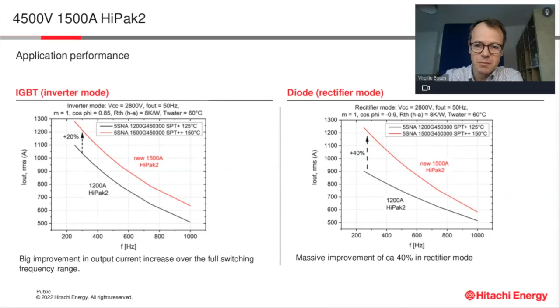Now, if we look at our press pack IGBT, which we call StakPak, it's what I like to call the strongest IGBT that exists out there. It comes in this type of square package. It's heavily used in grid applications where series connection is needed because the voltages are very high, starting from maybe SVC or STATCOMs at 30 kilovolt, but going up in HVDC stations up to 500 kilovolt. So series connection is needed.